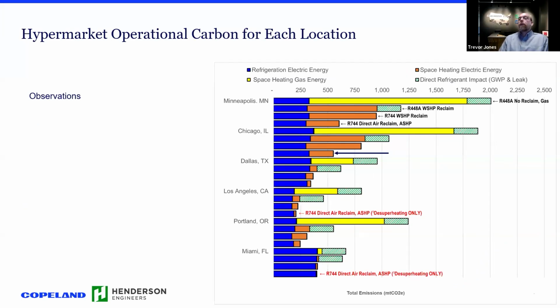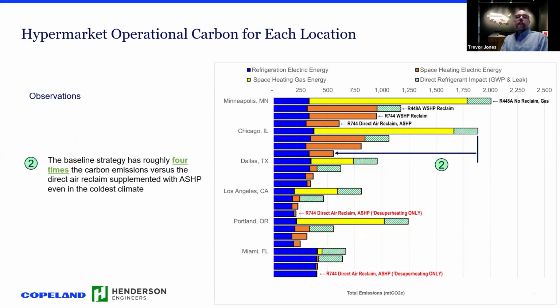So when we looked at the hypermarket operational carbon, again we see the air source heat pump outperforms the water source heat pump with reclaim, and that's due to the additional energy we're spending in electric heat throughout the year. At the very coldest points, the amount of electric heat is actually going to be the same for those very cold hours. It's just that the air source heat pump has much better efficiency in the more moderate temperatures. So our baseline for the hypermarket compared to our best case is roughly 4 times the operational carbon compared to air source heat pump with direct reclaim.